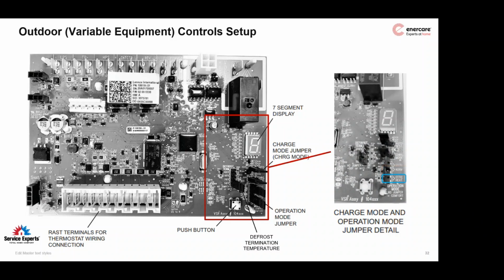Actually, going to back up before we move to the efficient heat. If you were to take one of these jumpers off, there's also a low mode or a cool mode. Basically it'll lock it at 125 psig and allow it to function consistently at 125 psig. It doesn't matter what the temperature is. It locks it in at a specific suction pressure regardless of temperature, so you're always going to get a consistent output temperature. I'd be more inclined to follow the most efficient operation. Just leave it the way it is. You don't have to adjust anything.